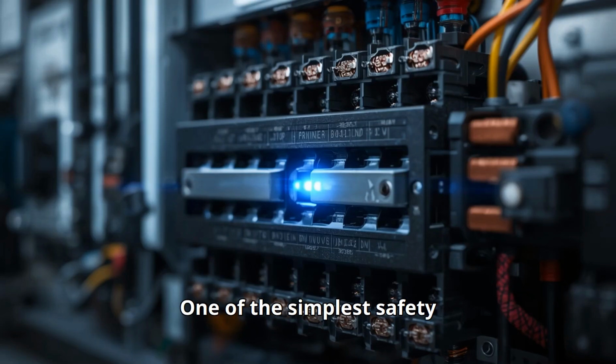The contactors that save lives. One of the simplest safety devices in electrical engineering is the magnetic contactor. A contactor is basically a heavy-duty electrical switch controlled by an electromagnet. When you press the start button, the contactor energizes. Its contacts close. The motor begins running. A holding circuit keeps the contactor energized. Everything works normally. Now imagine the power fails. The electromagnetic coil immediately loses power. The contacts open instantly. The motor stops.